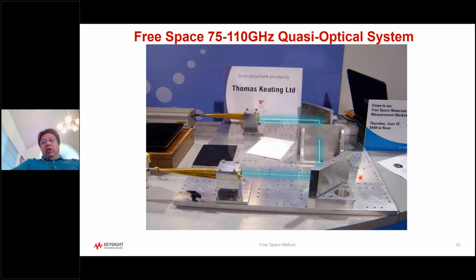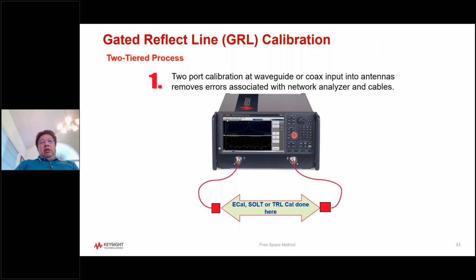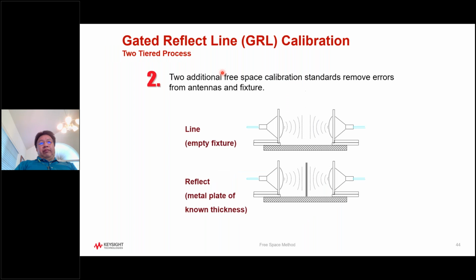This method is really good because of the precise position of the fixture and no actual movement. It requires calibration, of course, and the sample just goes here, and we do a two-port calibration with the network analyzer. No additional movement at higher frequency, less movement is better, so that your S parameter is accurate. To get accurate DF and DK values, you need accurate S parameters. For calibration, I just mentioned using the GRL calibration. In that case, it's much easier.